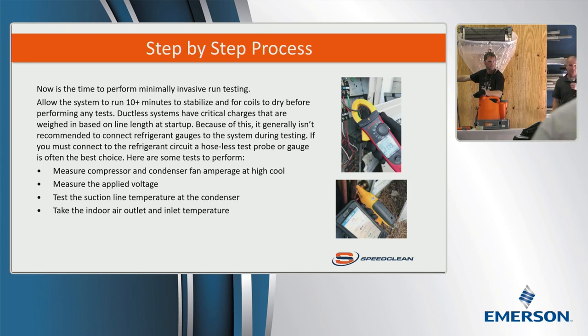Once you get done with that, it's the same things we already talked about: suction line temperature at the condenser. If you want to do superheat, you can do superheat. Just recognize it's going to be close to zero. 5 to 0 is going to be very typical on a ductless system running at high stage. Every manufacturer is a little different, but generally speaking, that's what you're going to see as a standard procedure.